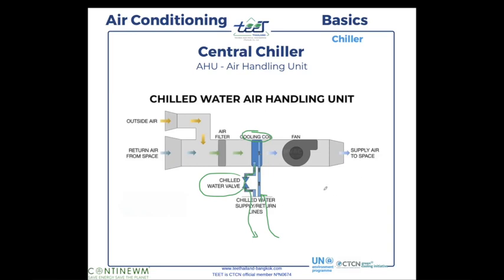Here you use power only for the fan. You use the power for the fan to suck the air and blow the air inside the room. But this is only 20%. The big energy is from the water. You remember, I gave you some idea. Here we measure kilowatt. Water in general, we will measure in ton or in BTU per hour. You remember all this? Now it's getting a little bit more clear.